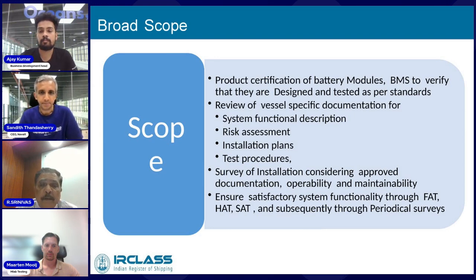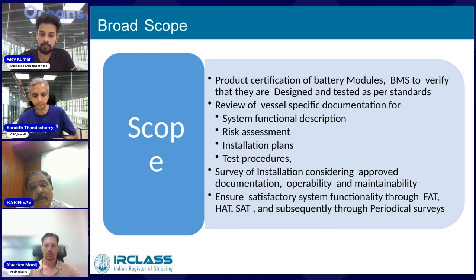Whether we need 100% redundancy, or it has to operate at 80%. What is the frequency of charging? Because if you're just crossing a river on a ferry, and you have 15 to 20 minutes of time with a facility to charge the battery on the other side, then the ampere capacity of the batteries can be suitably sized. But if you don't have that facility and have to come back after 5 to 6 trips, then it's a different ball game altogether. So the availability of charging facilities at the shore and the voyage duration make it very important to calculate the battery capacity.